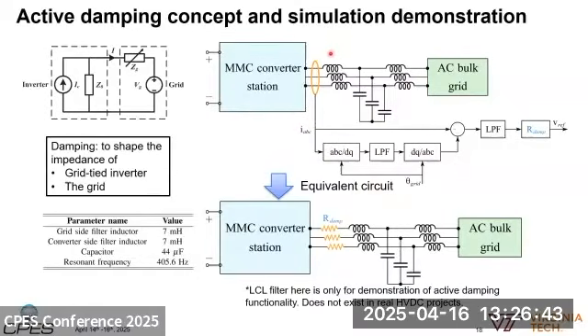We first sense the current at the PCC point, pass it through a high-pass filter, and multiply it by R_damp, the virtual resistance we want to add at the point of common coupling. This is equivalent to adding that virtual resistance, seen only by the high-frequency components of the current.